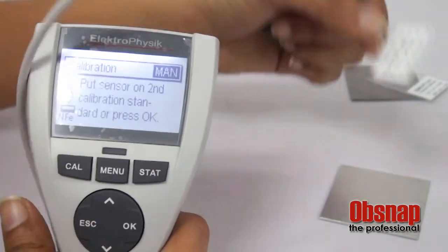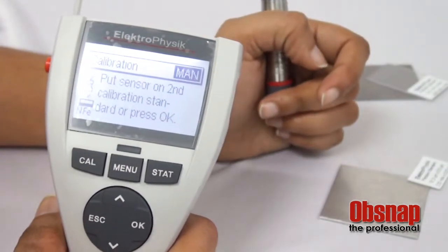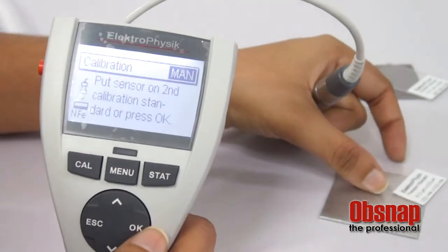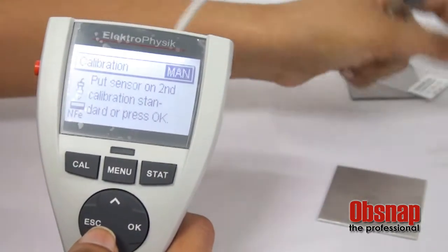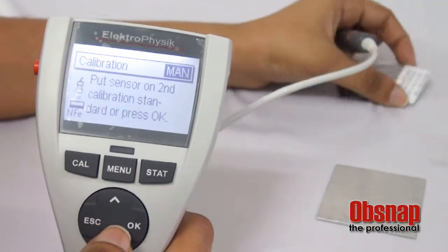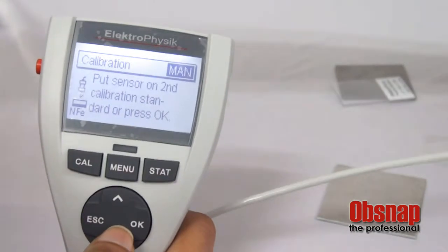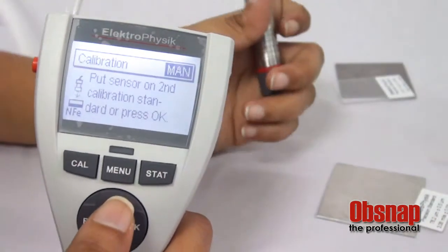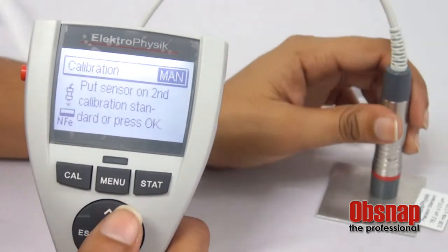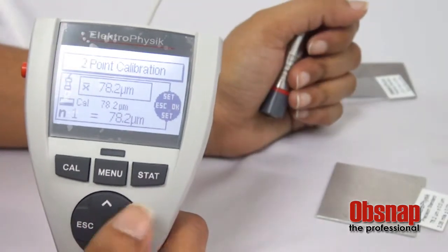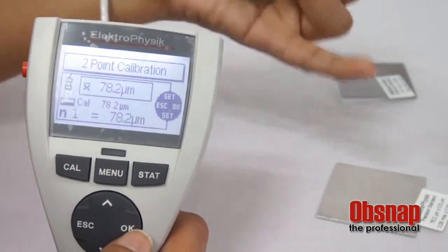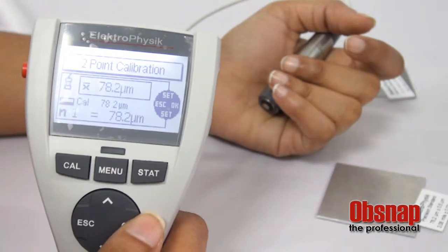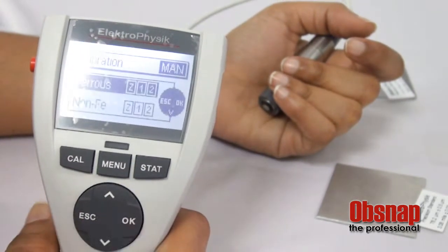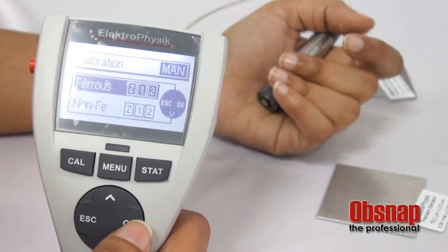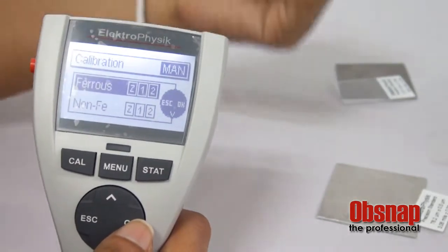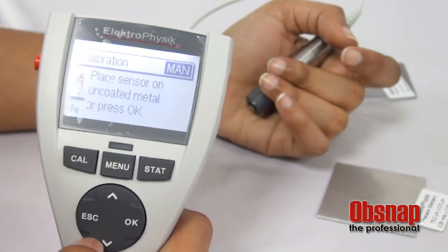So after you have performed the calibration, you click OK, and you even can put a second standard calibration precision foil and take the measurement. If the measurement is accurate, no need to perform setting, and you can click OK button, complete. Now it indicates the calibration for ferrous and non-ferrous is done. 2-point calibration is completed, so click OK button.